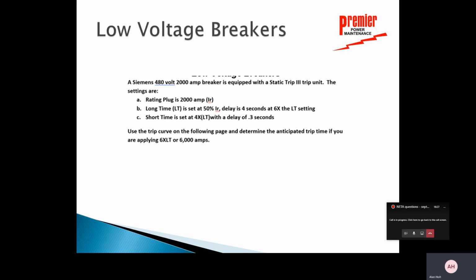All right, let's move on. We got a couple more questions here that we can discuss. This one's on low voltage breakers. I have a Siemens 480 volt 2000 amp breaker. It's equipped with a static trip 3 trip unit. Settings are, I've got a rating plug of 2000 amps. Long time setting is at 50% of that rating. So long time setting set at 1000 amps.